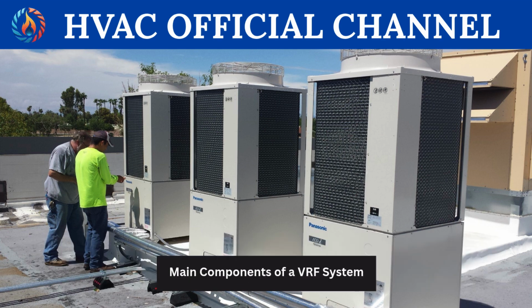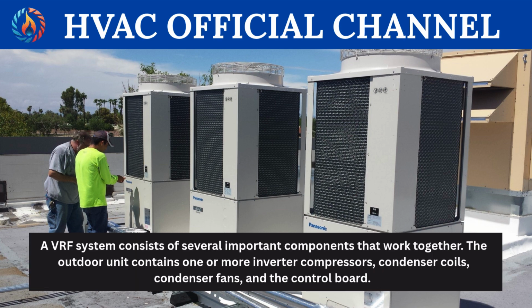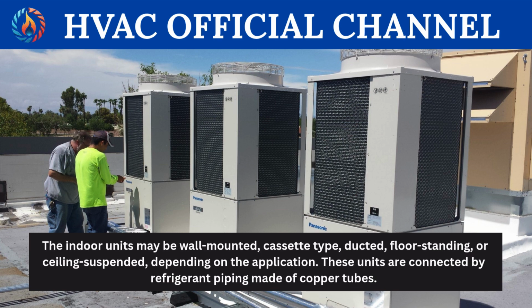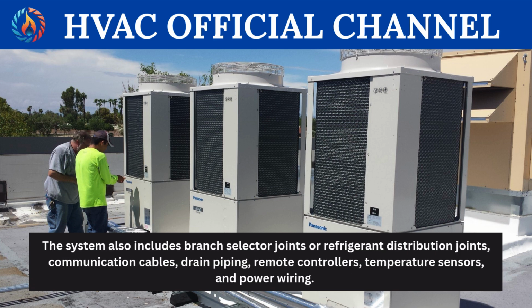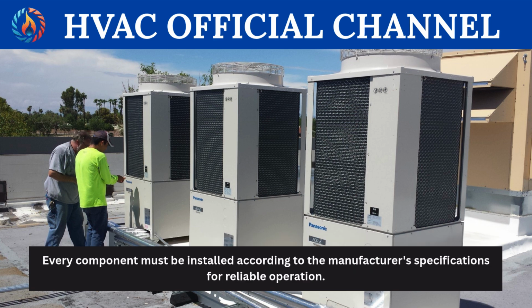Main components of a VRF system. A VRF system consists of several important components that work together. The outdoor unit contains one or more inverter compressors, condenser coils, condenser fans, and the control board. The indoor units may be wall-mounted, cassette-type, ducted, floor-standing, or ceiling-suspended, depending on the application. These units are connected by refrigerant piping made of copper tubes. The system also includes branch selector joints, or refrigerant distribution joints, communication cables, drain piping, remote controllers, temperature sensors, and power wiring. Every component must be installed according to the manufacturer's specifications for reliable operation.